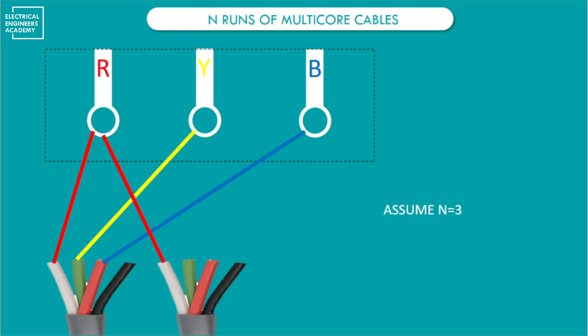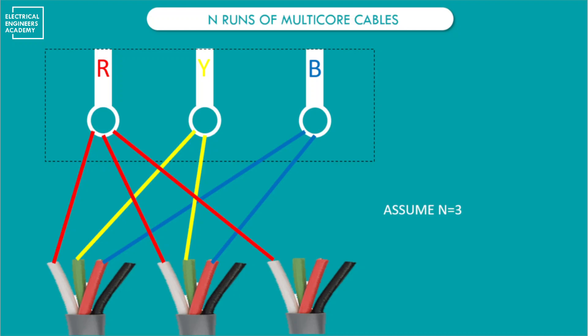For the second cable run: the first core connects to R, the second core connects to Y, and the third core connects to the B terminal. So now each terminal has two connections — one from each cable. R took two cables, Y took two cables, B took two cables, so n equals two. The number of runs is the number of current-carrying conductors connected to each terminal.